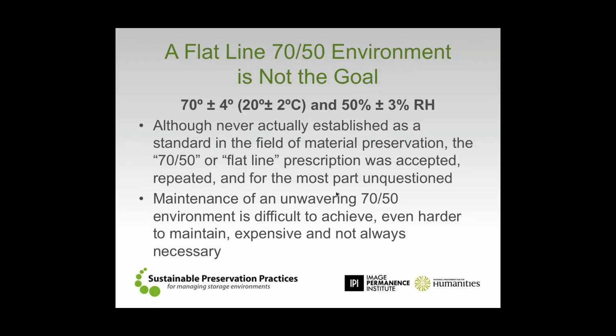To put it in succinct terms, or at least as succinct as I'm capable of, a flatline 70-50 environment, 70 degrees, 50% relative humidity, is 99 times out of 100, when it comes to preservation, not our goal. It's not anymore what we're trying to achieve. When we look at what is best for preservation, and also at year-round conditions throughout much of the United States, Canada, and elsewhere in the world, it's also often not the best condition from a flatline perspective for long-term sustainability and long-term energy savings.